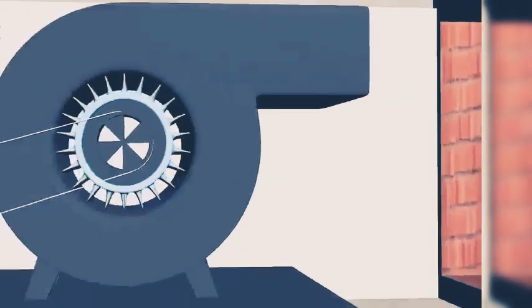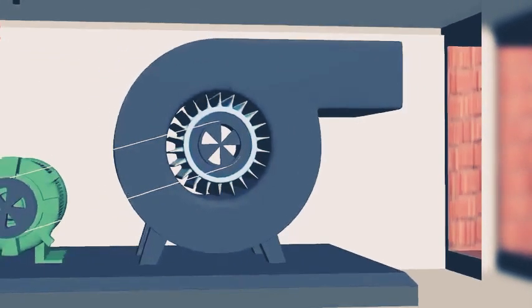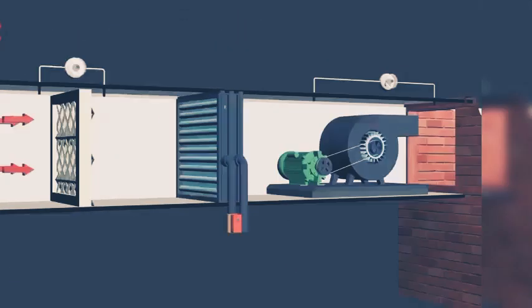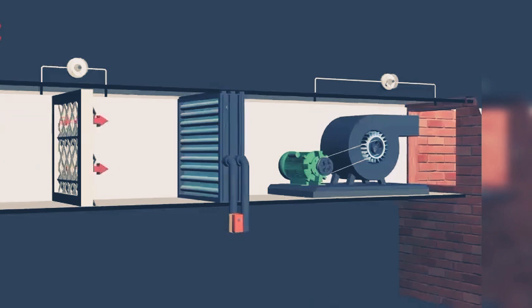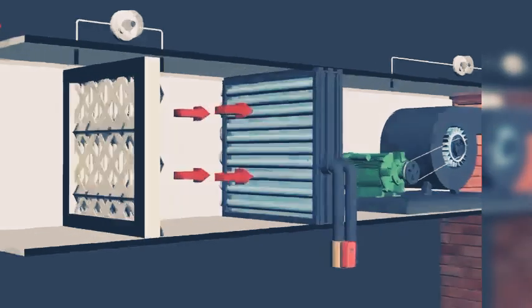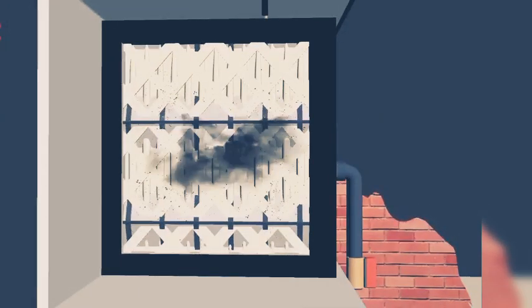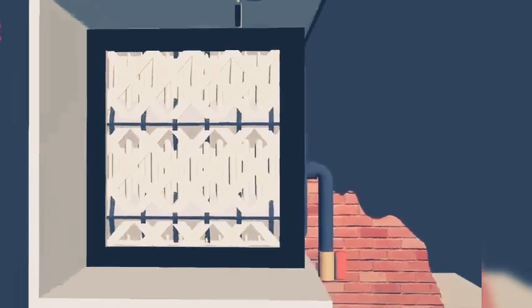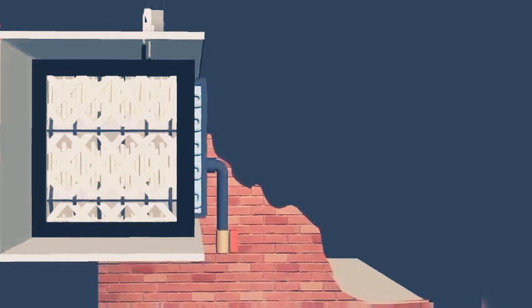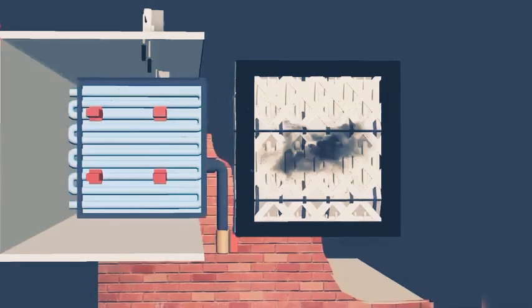Assume we are in summer and the hot space needs to be cooled. Once the FCU is turned on, the fan starts and the hot air in the space is sucked toward the FCU from the return grill. Air first enters the FCU through the filter. Any dust carried by the return air will stick on the filter surface, allowing only clean air to exit the filter and move forward. Hence, this filter requires cleaning on a scheduled basis. This is often done on a monthly or quarterly basis by simply pulling the filter by hand, washing it and replacing it back.